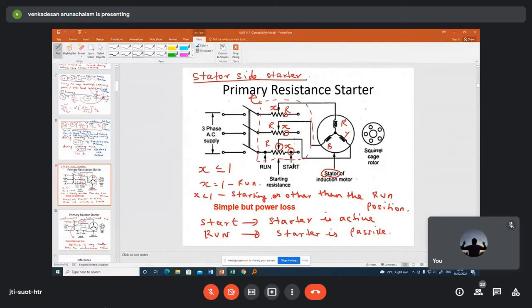Okay, and X is the fraction with which the resistance value is added to the stator winding. So during starting condition X will be less than 1, and during running condition X is equal to 1. X less than 1 means some fraction of resistance is added to the stator winding. So this is the point X in this example.